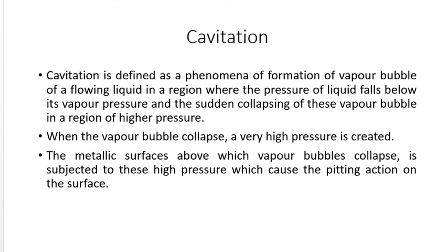When the vapor bubbles collapse, a very high pressure is created, and the metallic surface on which this pressure is subjected suffers a pitting action. These cavities formed on the metallic surface by the pitting action are called cavitation. Considerable noise and vibrations are also produced because of the sudden collapsing of the vapor bubbles. Cavitation includes formation of vapor bubbles of the flowing liquid and collapsing of the vapor bubbles.